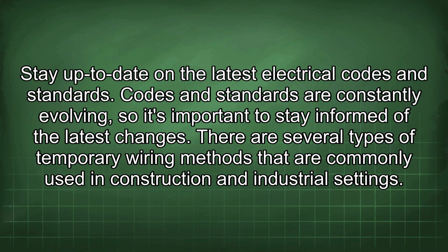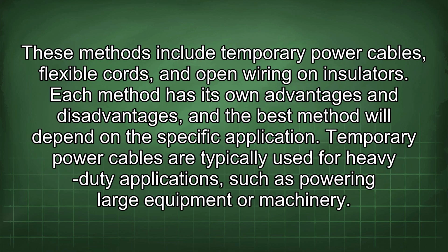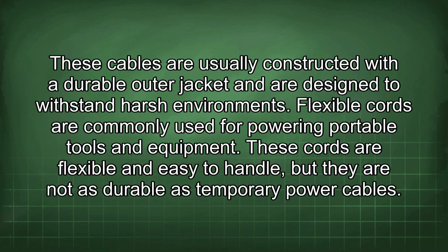There are several types of temporary wiring methods that are commonly used in construction and industrial settings. These methods include temporary power cables, flexible cords, and open wiring on insulators. Each method has its own advantages and disadvantages, and the best method will depend on the specific application. Temporary power cables are typically used for heavy-duty applications such as powering large equipment or machinery. These cables are usually constructed with a durable outer jacket and are designed to withstand harsh environments. Flexible cords are commonly used for powering portable tools and equipment. These cords are flexible and easy to handle, but they are not as durable as temporary power cables.